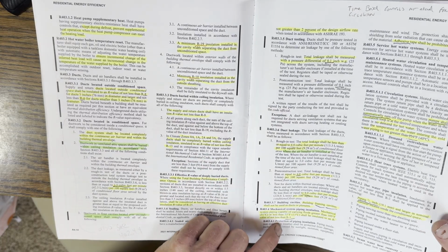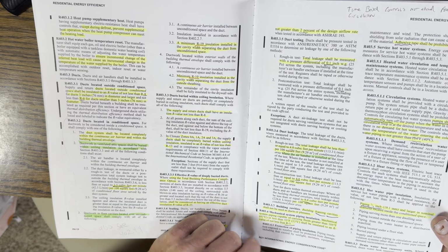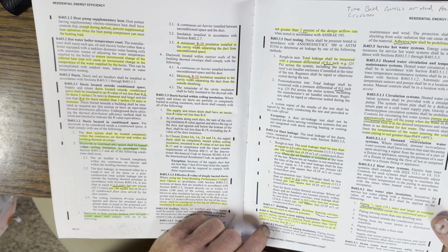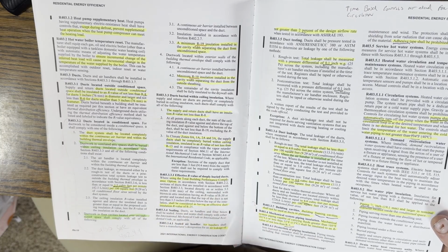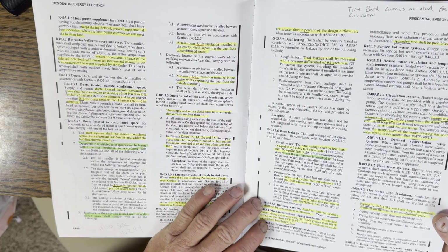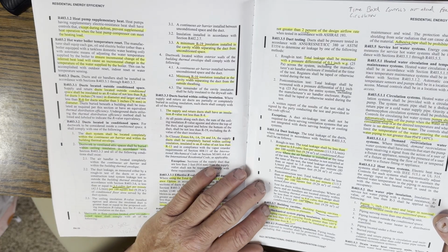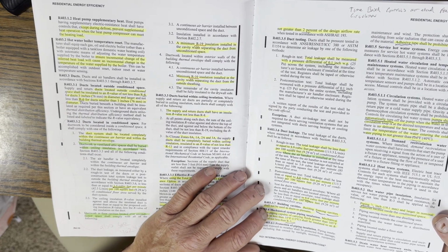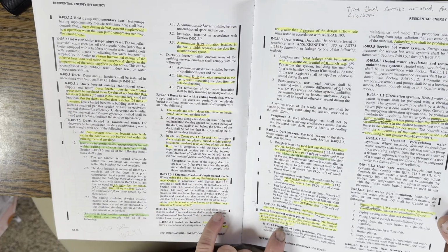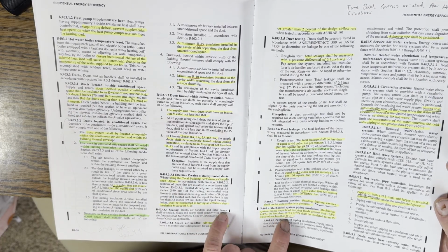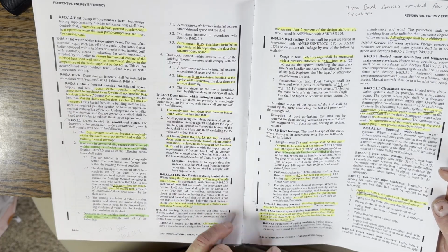Yeah, you had a question here. The question was, I can't remember the size of the piping. Mechanical systems, it was a 200 degree Fahrenheit liquid, transferring in a pipe. And I think it was through conditioned space. What insulation did you need? In this case, it was R3 as a minimum. That was there.